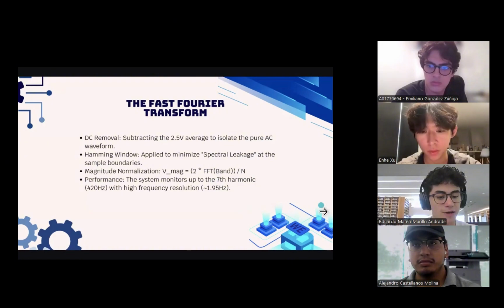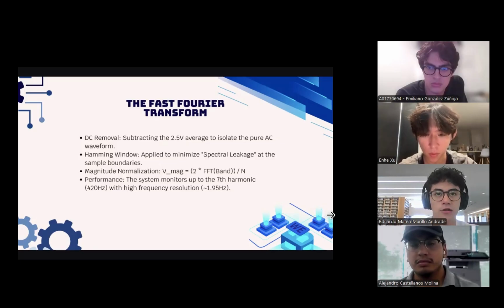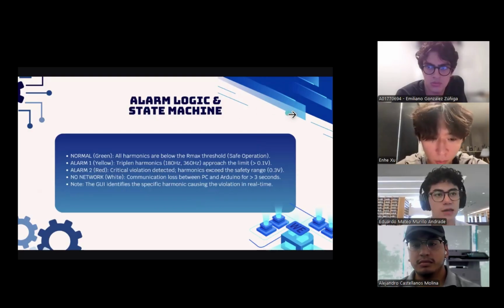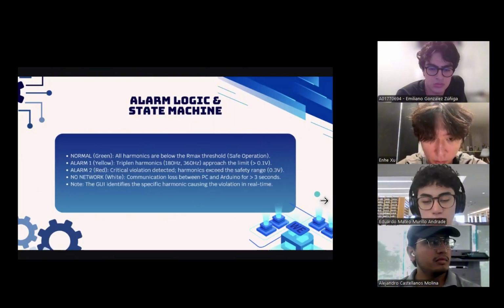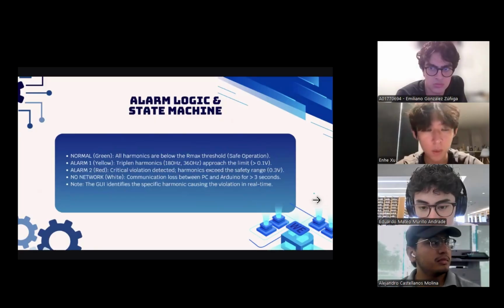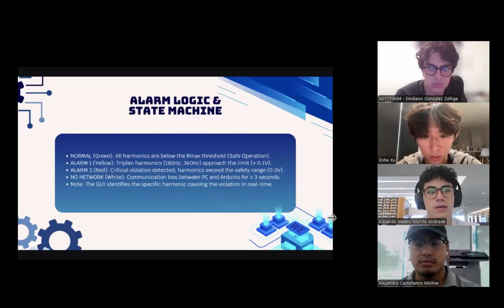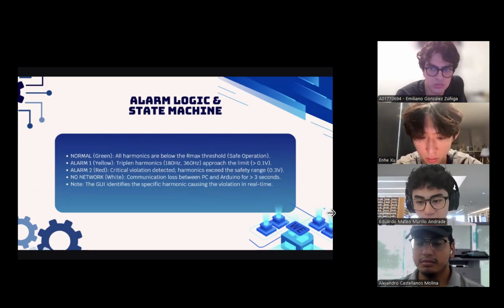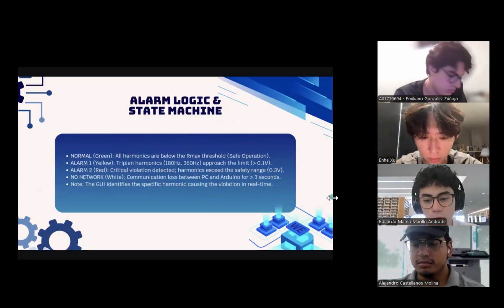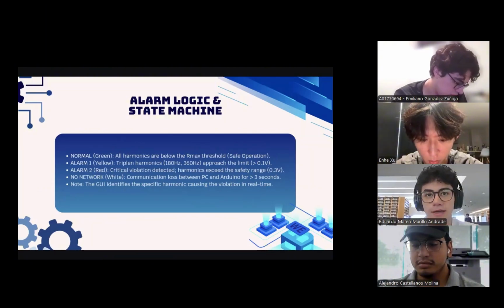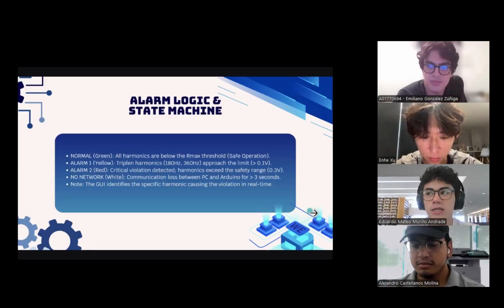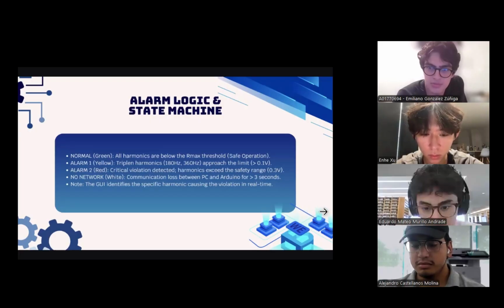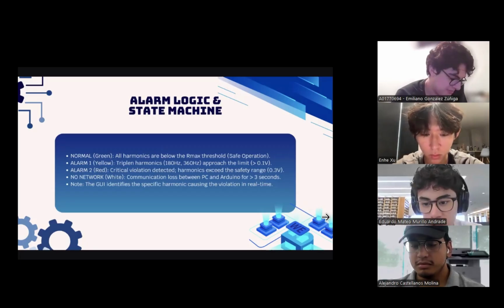And finally, the performance is optimized, allowing our system to track up to 7 harmonics, which is 420 hertz, while maintaining an incredible frequency resolution of 1.95 hertz. In the following slide, we can see the functioning of the LEDs. The green one means a safe state. The yellow one lights up when the normalization is up to 0.1 volts, being a be-careful zone, and then we have the red critical zone when the value of the normalization is above 0.3. The white LED is only turned on when the connection between the Arduino and the laptop is not found in 3 seconds. And the GUI identifies the specific harmonic causing the violation in real time.